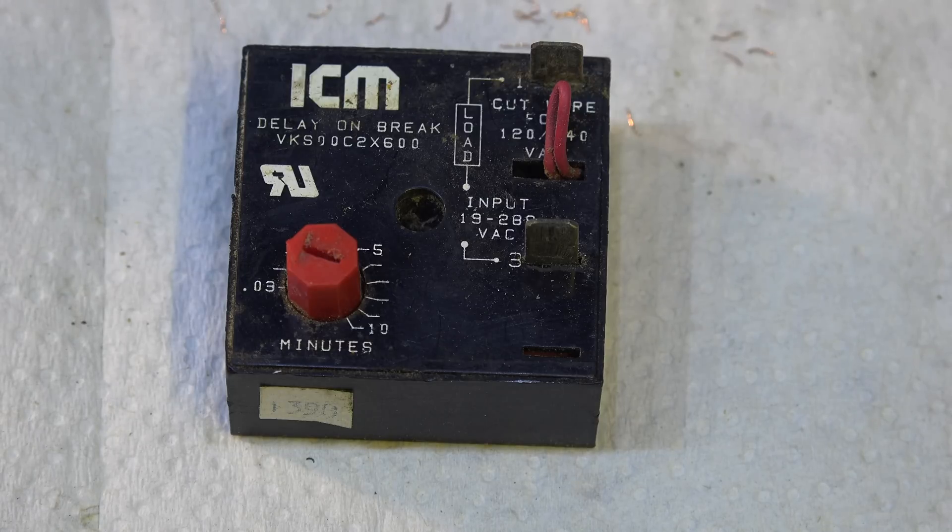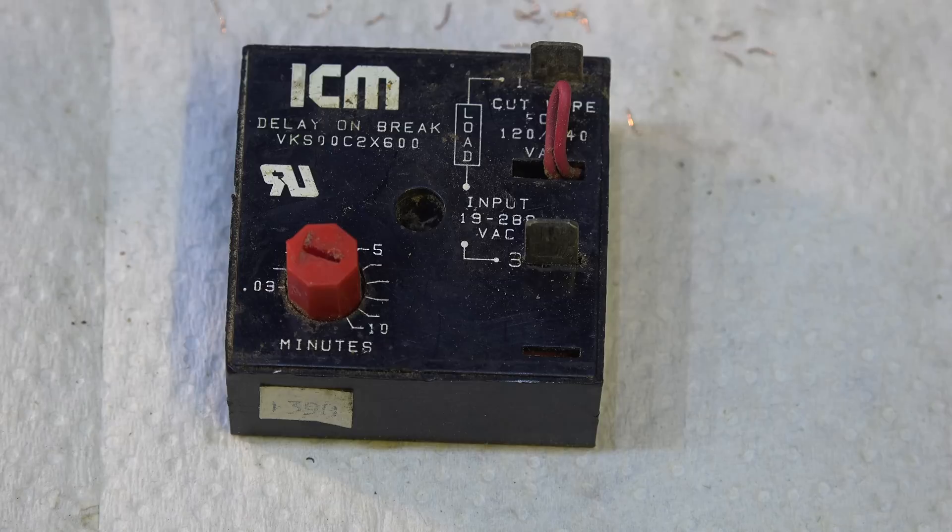It's harder on the compressor because it tries to start, it overheats and kicks off its internal overload. So in order to stop that, and sometimes it blows fuses too, we can put these timers in here.